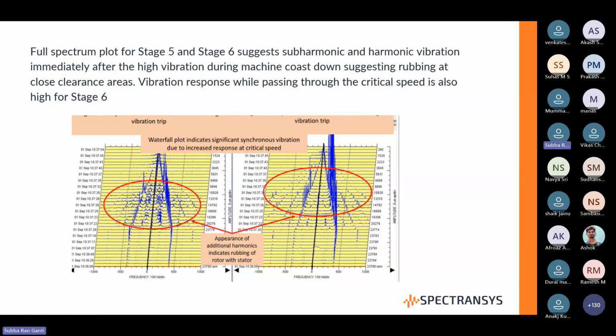This is the data taken from a compressor. It's an integrally geared compressor, and the stage 5-6 had some high vibration tripping. So this is the full spectrum coming from, on the left side, stage 5, I think, and on the right side stage 6 or so. When the machine is normally running, you can see that the vibration amplitudes up to a certain speed are very low.